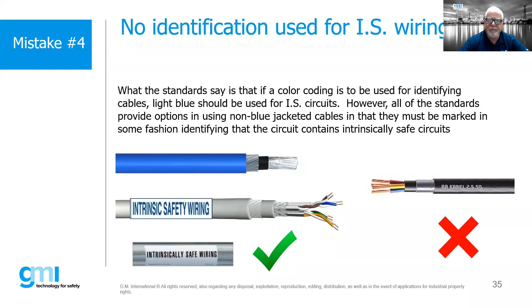The cable on the right-hand side, we could use that cable, right? But we'd have to put a tag on it. We'd have to put something on there that tells us that this is intrinsically safe. So in a pinch, if you wind up on a project and you find that you've got some non-light blue cable, a good solution is to get some light blue heat shrink, right? The labeling shall be permanent. Don't just put blue tape. That's not acceptable. We want to put something that's actually a permanent marker on that cable to identify it as intrinsically safe.